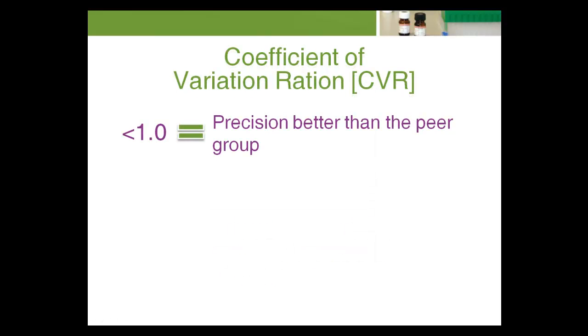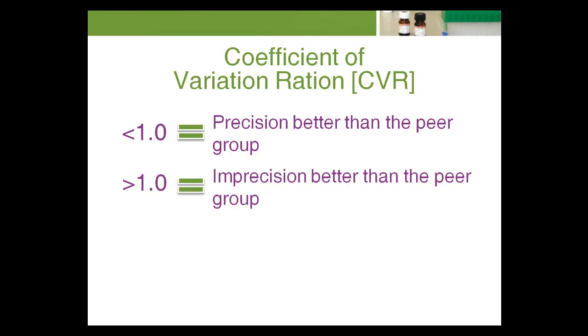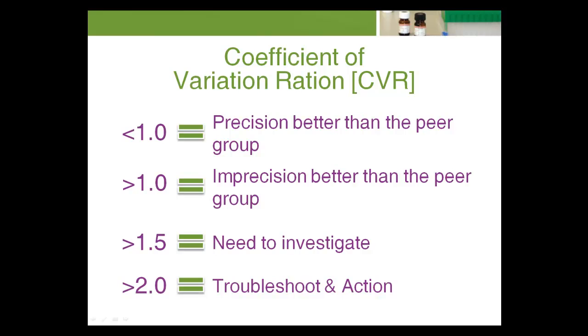Any ratio less than 1 indicates that precision is better than the peer group. Any score greater than 1 indicates that imprecision is larger. Ratios greater than 1.5 indicate a need to investigate the cause of imprecision, and any ratio of 2 or greater usually indicates a need for troubleshooting and corrective action. Something in the test system is causing the increased imprecision, and patient test results may not be entirely reliable. Certainly repeated tests such as glucose for diabetic patients, or prothrombin times for patients taking Coumadin, will not be reliable when the imprecision is high.